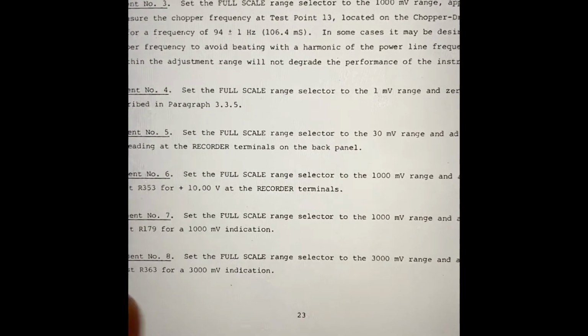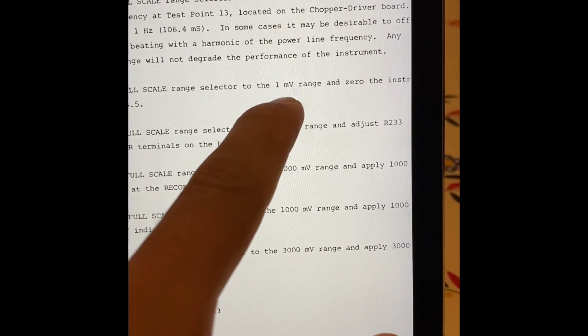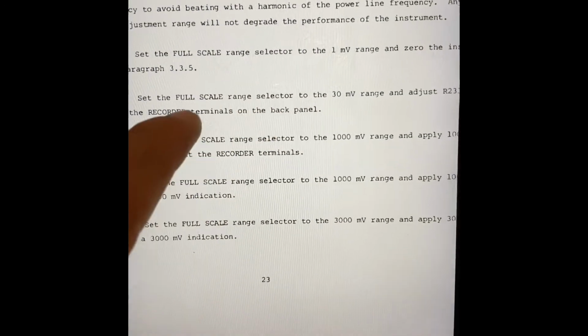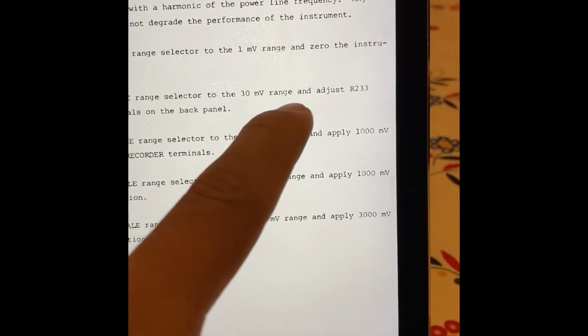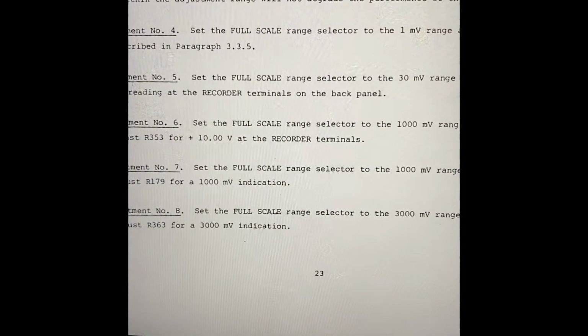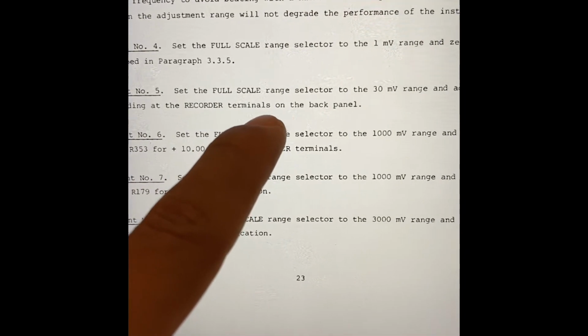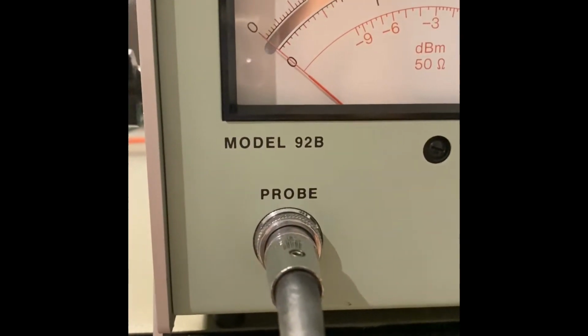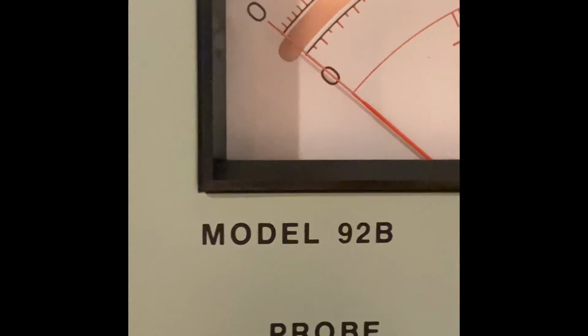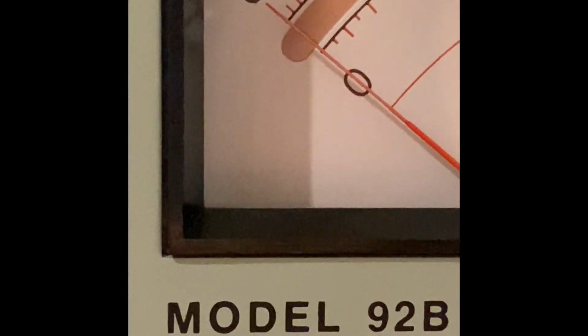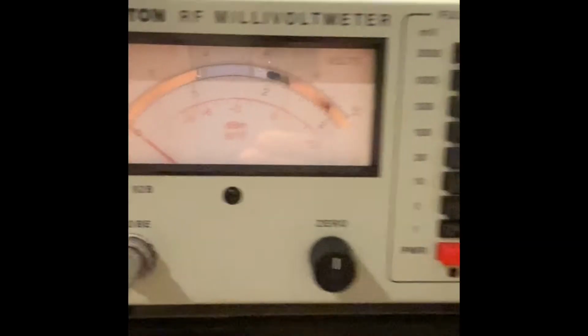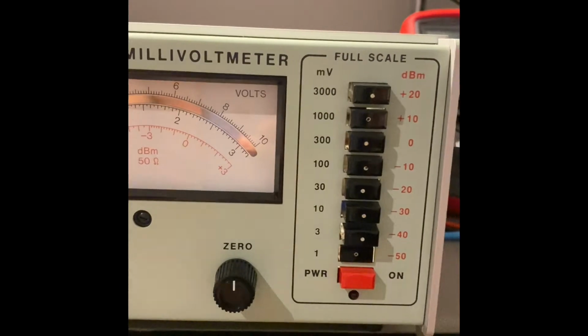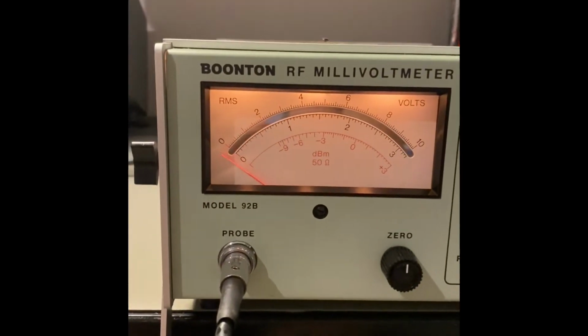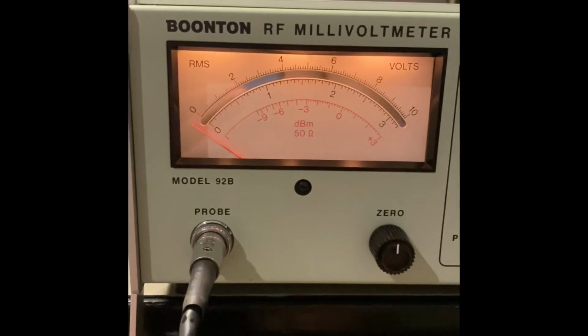Now the next step is to set the full scale range selector to the 1 millivolt range, which is the lowest one, and zero the instrument, and then set the 30 millivolt range and adjust R233 for a zero reading on the recorder terminals on the back panel. So first of all, we want to check that when the instrument is off, we've got the needle at 0. Okay, it looks like it's fine. Now we switch the instrument on, and we try to zero the instrument. Now I have some issues with this instrument.